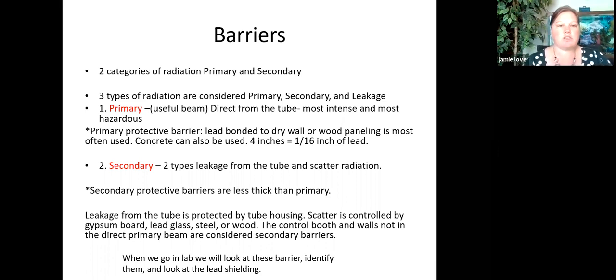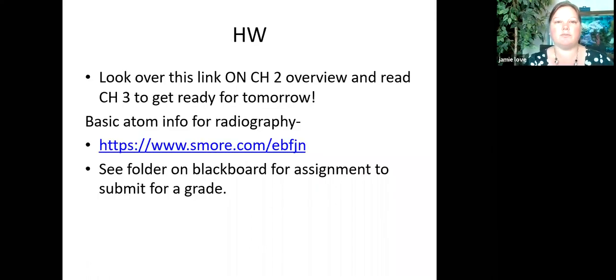So scatter is controlled by different things. It could be lead glass, steel, wood, this gypsum board material in the walls. The control booth, the walls, and the doors, as long as they're not in the primary beam, are secondary barriers. We'll look at that in the lab tomorrow, along with the lead shielding that we have.